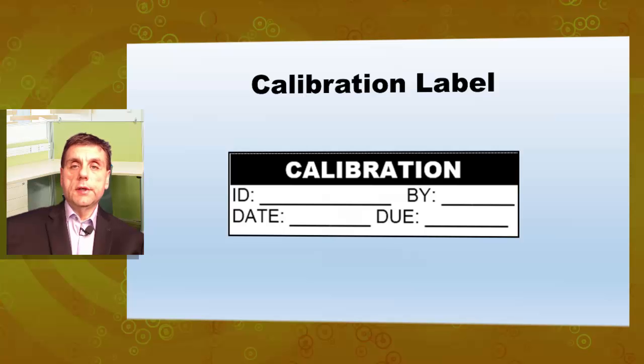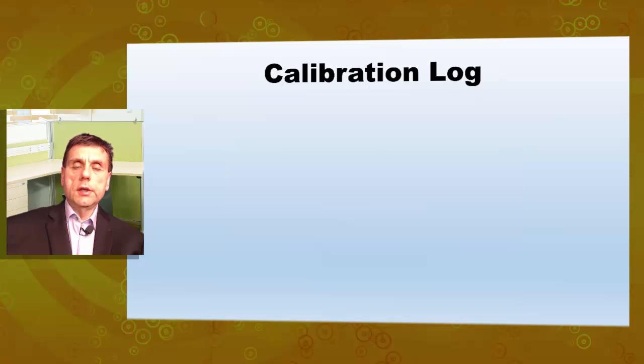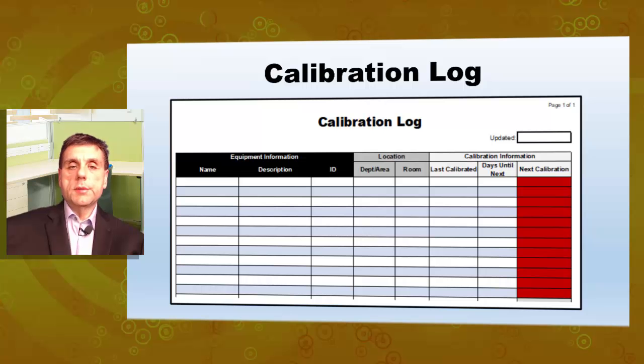Calibration label should identify the equipment that needs to be calibrated with an ID, the identification number, which we discussed previously. A date of calibration should be on the label, and the due date for the next calibration depends on the frequency or the calibration interval that was previously determined by the organization. It should also bear the name or some identification of the person who performed the calibration. Calibration log is the main document that would specify the equipment information, such as a name, description, and ID, the identification, then location of the equipment, for example, department or area or a specific location, and the calibration information like last calibration, calibration interval, and the next due date of calibration.